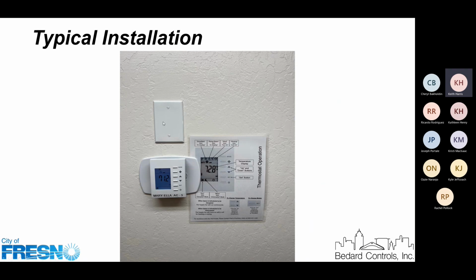But also, a lot of the older systems had a mechanical timer, or what we refer to as a bypass timer. We are typically removing that and putting a cover plate on there because the occupied, unoccupied mode through the set button does the same thing as this occupied mechanical timer used to do. So you'll see sometimes a blank faceplate where that timer used to be. In most cases, they're not hooked up anymore, but we're trying to clean it up and make it look a little nicer. But the unoccupied and occupied function that mechanical timer provided is now done through the set button.